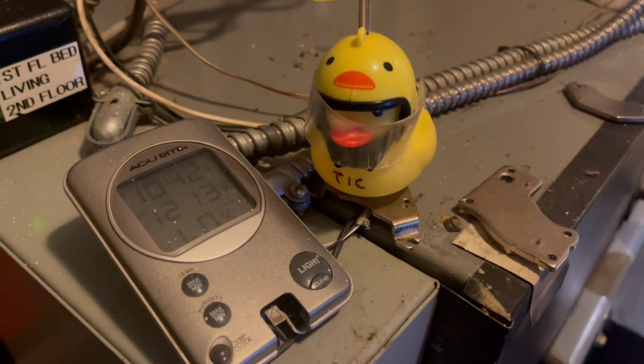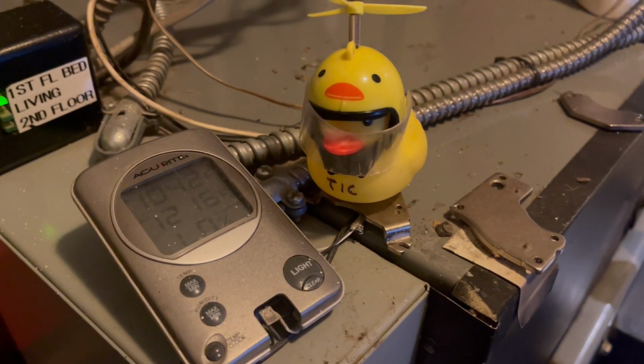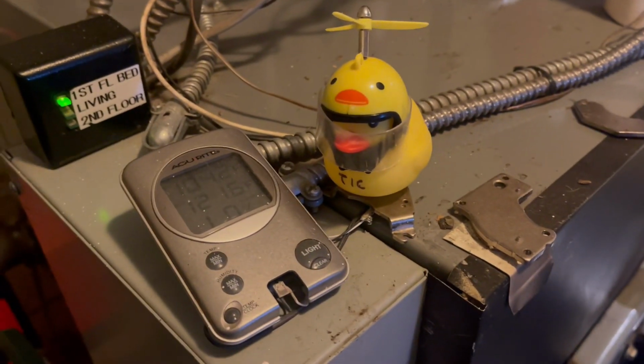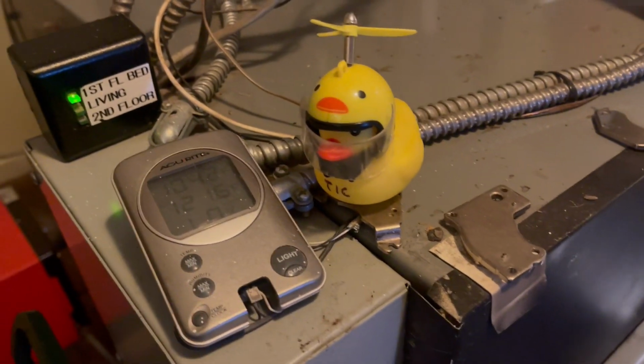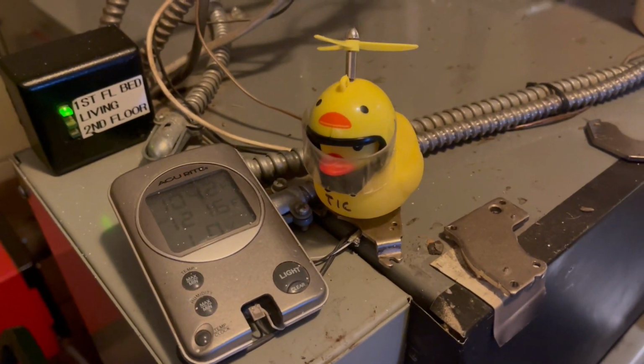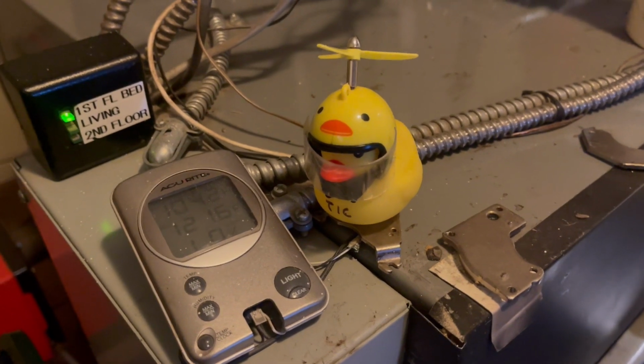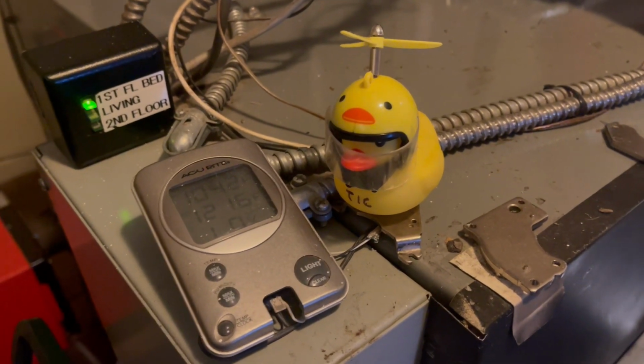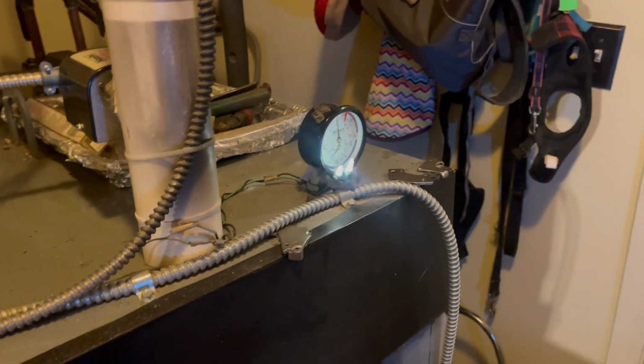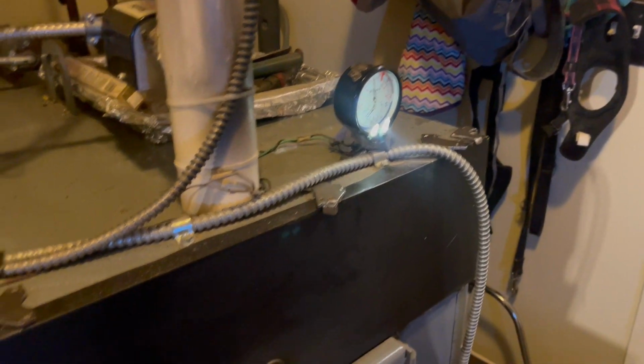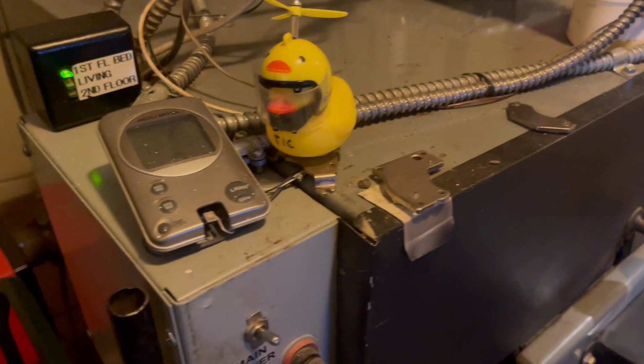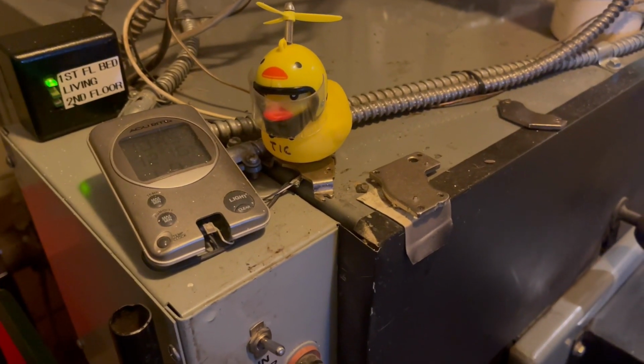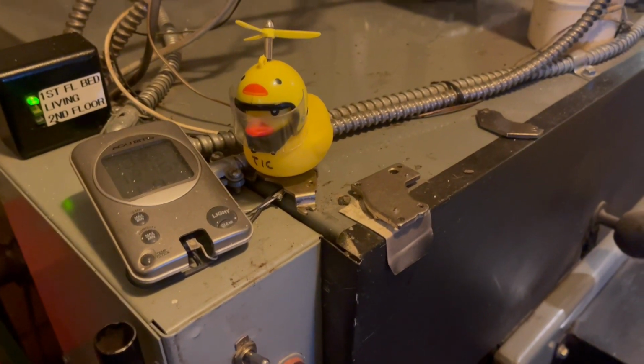Now, Tick wants to know why you would go through so much trouble and not just hook the north wing of the house up to the domestic hot water coil back there. Two reasons. One, it's too far away and you'd have to pre-order hot water like 10 minutes before you needed it. Number two is that my daughter gets up before I may have the boiler to temperature, which means she would not have hot water in the morning. As it is, I've pre-made 80 gallons of hot water.